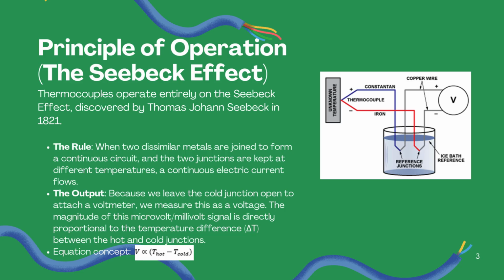Now I'm going to talk about the principle of operation, which is the Seebeck effect. Thermocouples operate entirely on the Seebeck effect discovered by Thomas Johann Seebeck in 1821. The rule is when two dissimilar metals are joined to form a continuous circuit and the two junctions are kept at different temperatures, a continuous electric current flows. So the output can be produced because we leave the cold junction open to attach a voltmeter. We measure this as a voltage. The magnitude of this microvolt or millivolt signal is directly proportional to the temperature difference, which is delta T, between the hot and cold junctions.